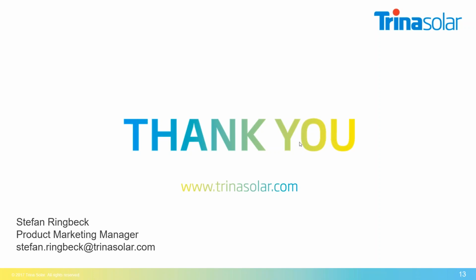That's a question about the 1500 volt. In most European countries and even in most countries around the globe, there's a so-called low voltage directive. In most countries, the low voltage directive defines low voltage as below 1500 volt. That means as long as you're below or up to 1500 volt, you can work according to the low voltage directive. If you exceed this, you have to go to medium voltage, which adds additional requirements.